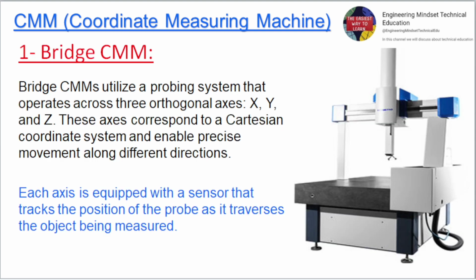1. Bridge CMM. Bridge CMMs utilize a probing system that operates across three orthogonal axes, x, y, and z. These axes correspond to a Cartesian coordinate system and enable precise movement along different directions. Each axis is equipped with a sensor that tracks the position of the probe as it traverses the object being measured.